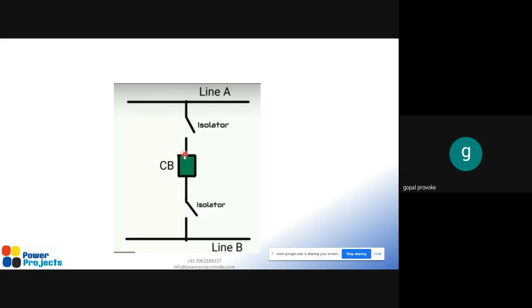Since the circuit breaker is open, there won't be any current flow between line A and line B. We can directly close the isolator, and then we can also close the isolator of line B. There won't be any current flow between line A and line B since the circuit breaker is open. And at last we can close the circuit breaker.